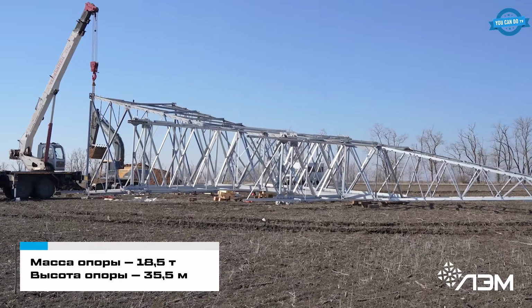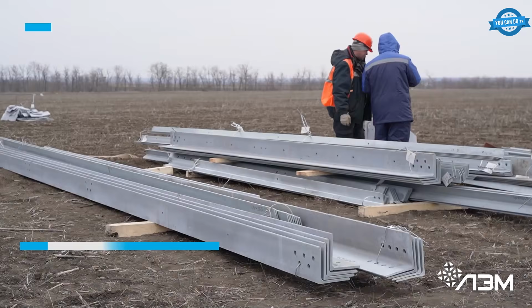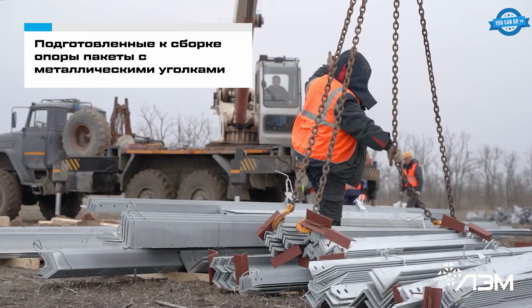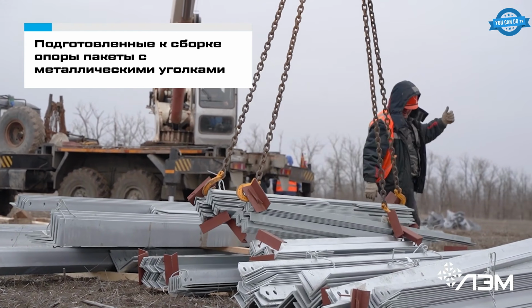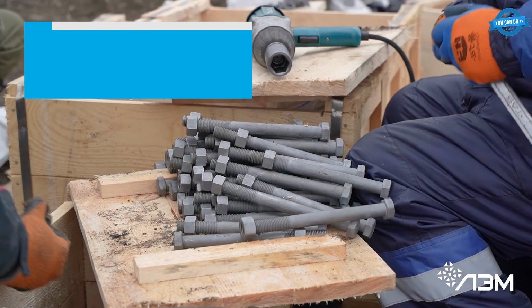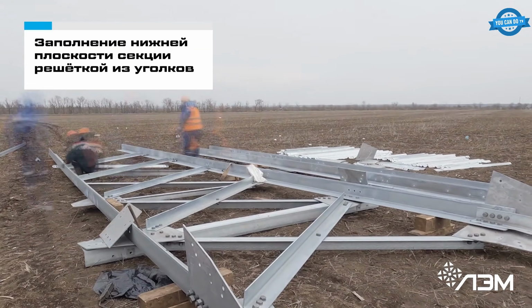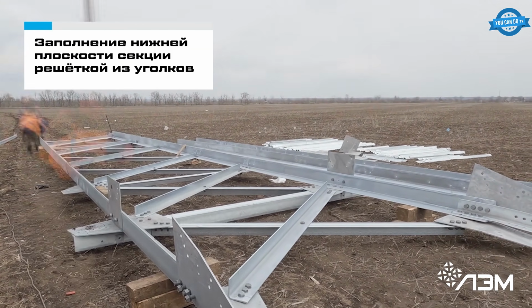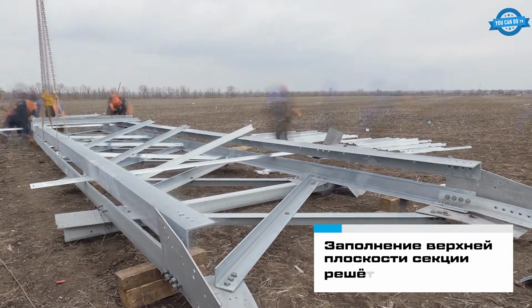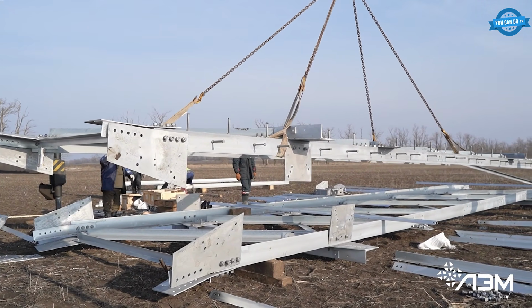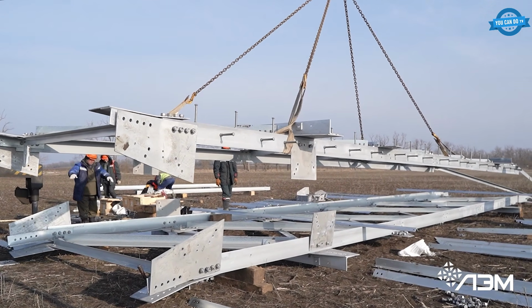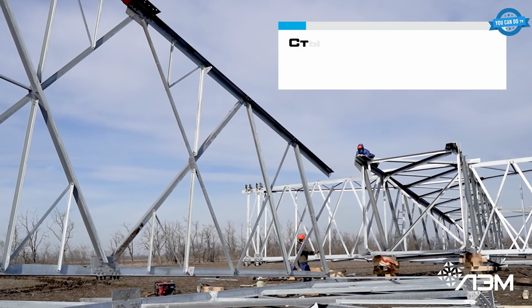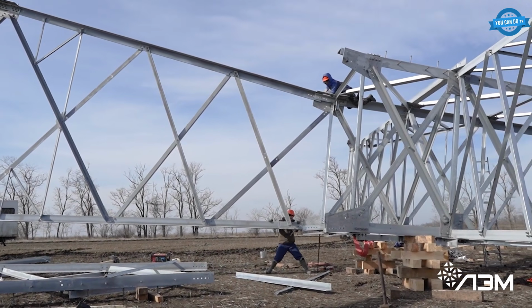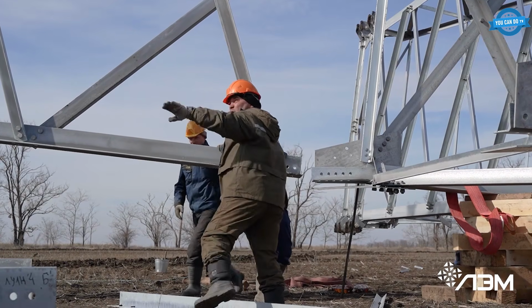Bolt 18.5 tons of steel angle into a 35.5 meter tower lying flat on the ground, and the bolts themselves become the weak point until anti-tamper nuts solve a problem most people never knew existed. Anchor Corner Tower U331 assembly begins with sorting steel angle bundles delivered to site and test-fitting nuts on every step bolt to verify thread quality. The lower body frame goes together flat, the bottom lattice plane first, then the upper plane raised with crane support. A pre-assembled side panel lifts in and bolts perpendicular into the main frame, giving the structure its 3-dimensional shape.